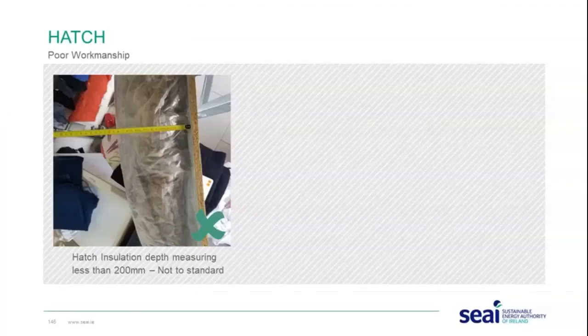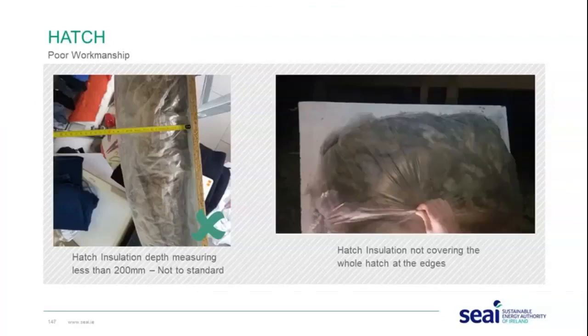Poor workmanship examples on hatches include insulation depth measuring less than 200 millimetres, which does not meet standards, and hatch insulation not covering the whole of the hatch — the insulation should cover the entire hatch area including the edges.